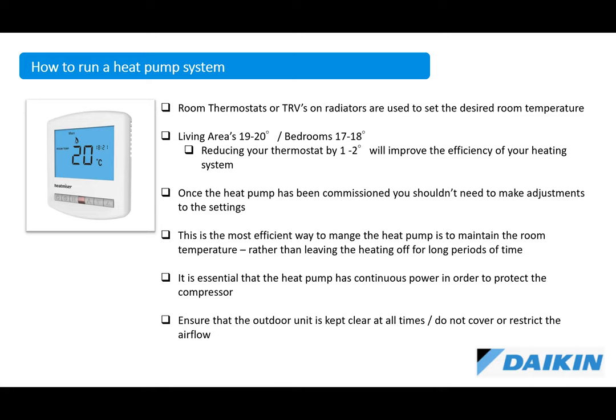So just two other important factors. It's really important that you don't turn off the power to your heat pump, because your heat pump has programs built in to manage it and certainly to protect the compressor. So when there's very cold temperatures outside, you're going to see a lot of water running off the heat pump. And during times of high humidity, you're going to see a lot of water running off the heat pump. And it's important that that water can flow easily away, that it doesn't sit underneath the heat pump and start to freeze back up into the heat pump.